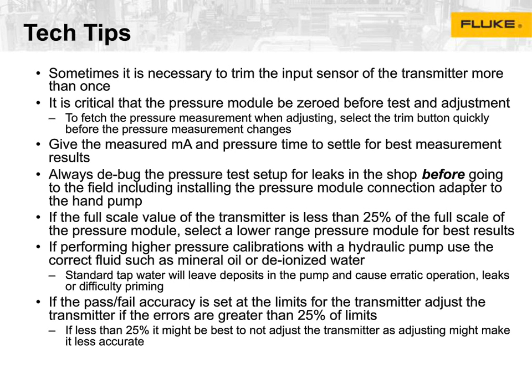We talked about allowing milliamps and pressure to settle, and then I'm going to repeat it again and again. Debug your test setup in the shop before you go out there. It will save you so much time and aggravation if you're out in the middle of nowhere, or if you're in a far corner of the facility and you've got a test setup that's leaking and you can hear it. That's not where you want to be. You'd much prefer to do that in the shop. Make sure that you are using the right fluids. I've said it 3 times now in this presentation. It's probably one of the most critical things when using hydraulic pumps.